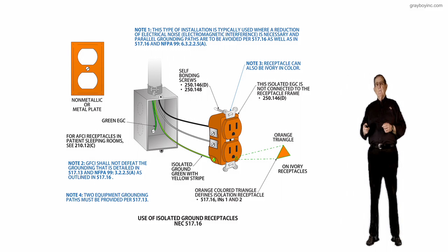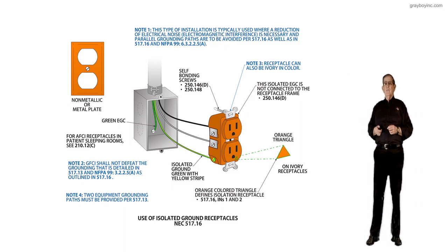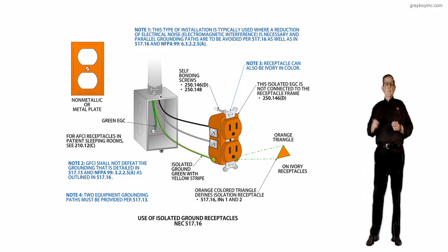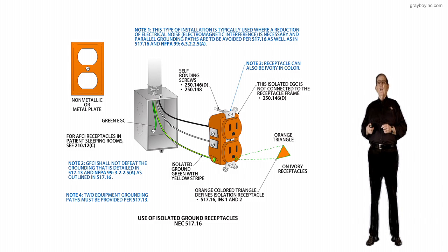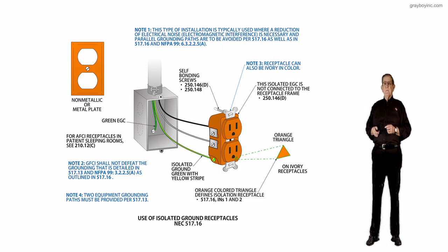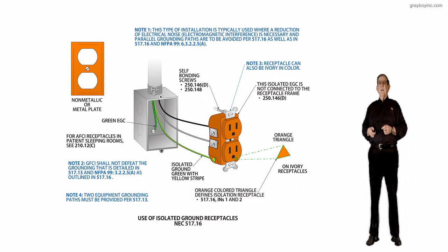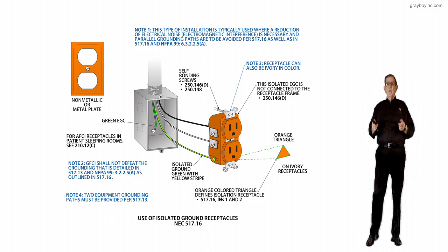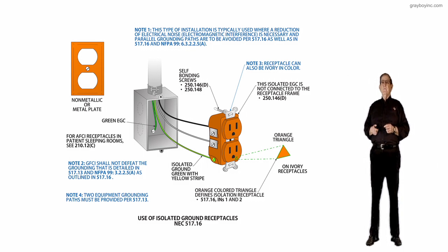Notice a lot of the existing receptacles are just solid orange, as you see in the illustration. Then some of the newer ones, instead of having to gear up as a manufacturer for a solid orange, they may have it gray with a little triangle on it. The orange colored triangle defines isolation receptacle, and notice it's on an ivory-type receptacle. This receptacle is outlined in 517.16, informational notes 1 and 2, when it's installed and used in healthcare-type facilities.